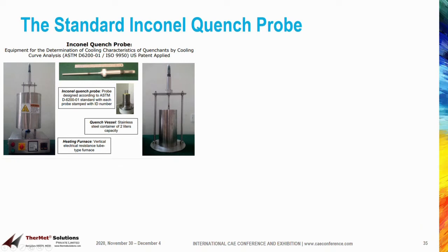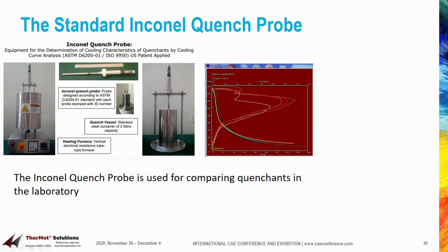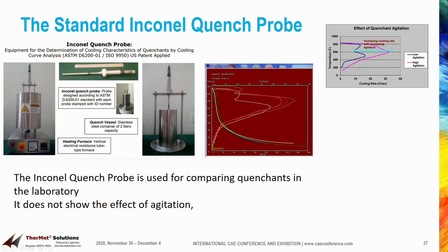Equipment used for measuring the cooling characteristics of quenchants in the heat treatment industry is the Inconel quench probe defined under ASTM D6200 and ISO 9950. The Inconel probe can be used for comparing quenchants only under laboratory conditions. It is common knowledge that quenchants behave differently when agitated, as is the case in the plant.